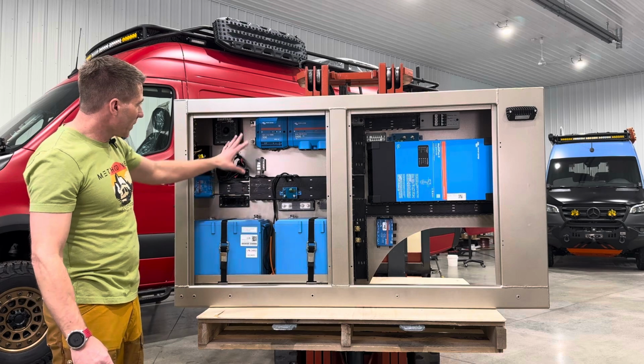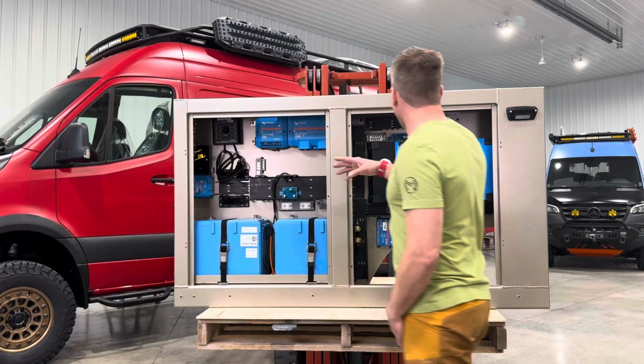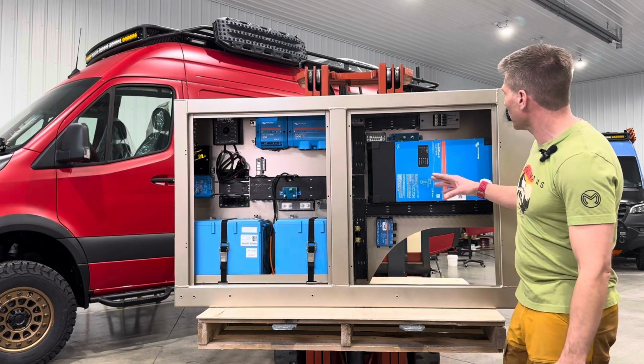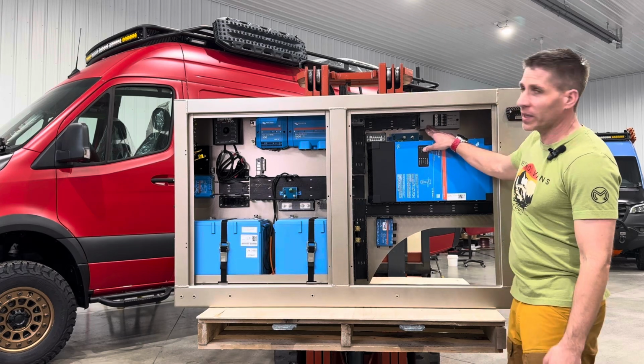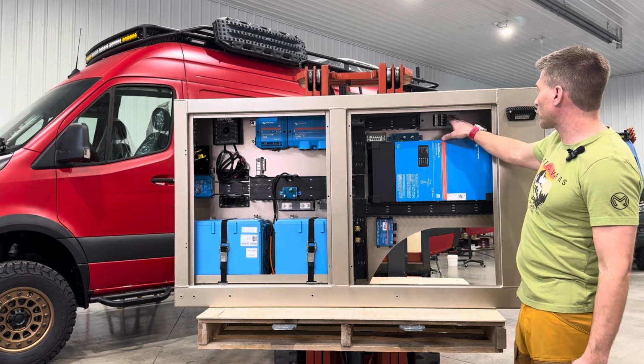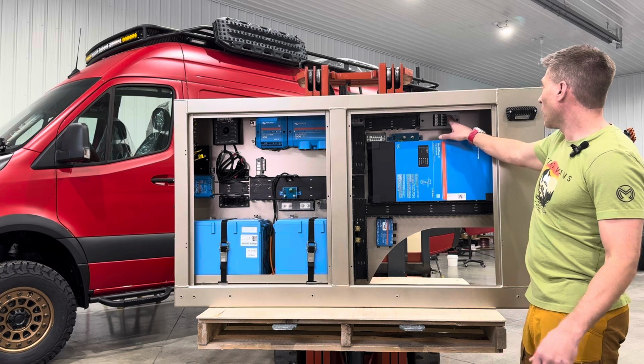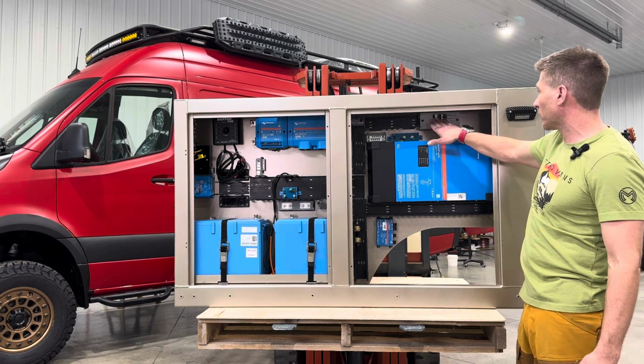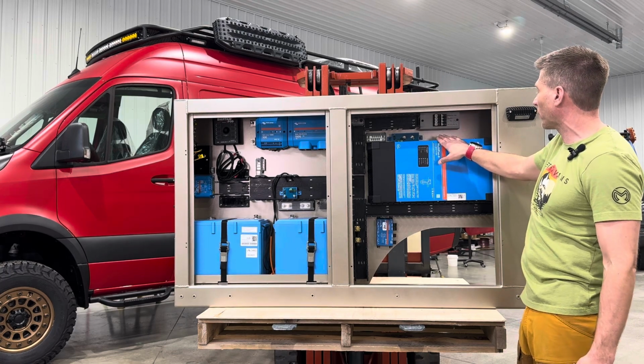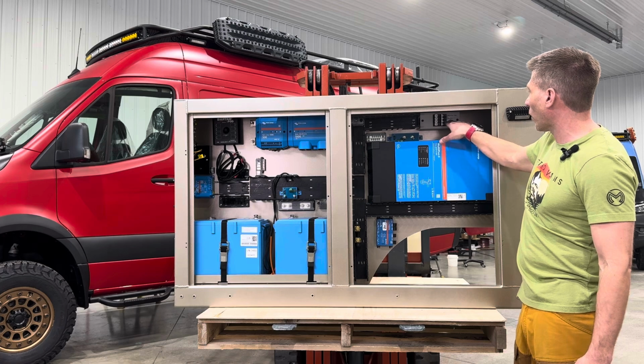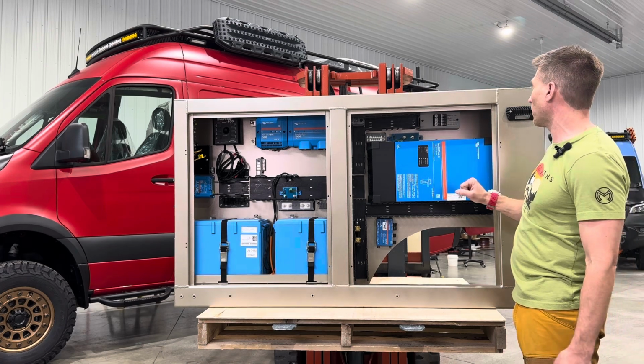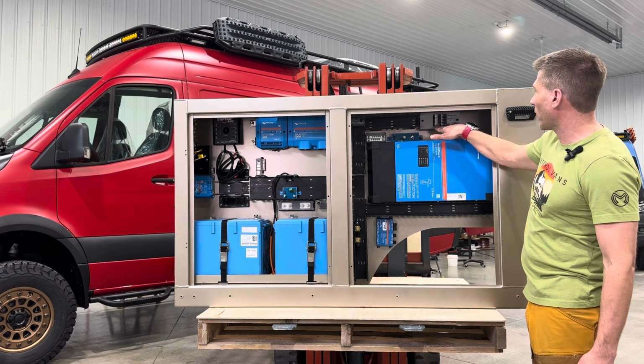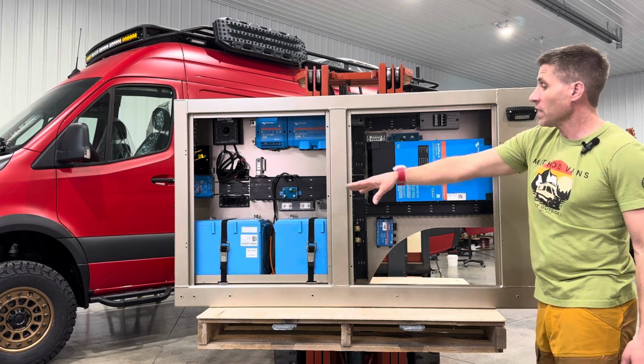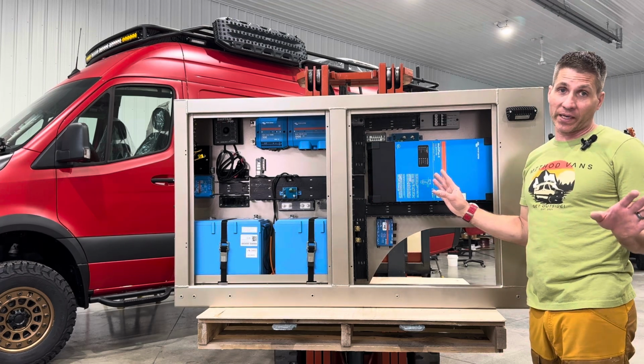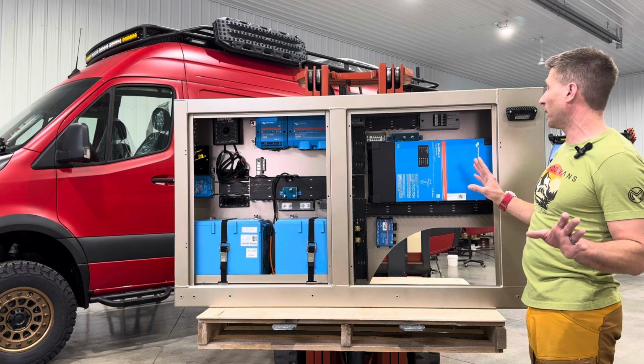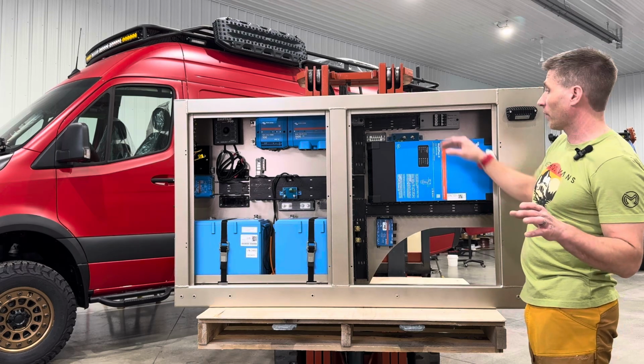From here, if we pop over, we have some other componentry. We have a breaker box with our solar disconnect - solar in and solar out - which we can turn on and off inside this breaker box. We have a breaker for our alternator regulator inside this box, and we also have a breaker for our battery heating. So if we want to, in the summer, just turn the battery heating off to have no risk of it coming on by mistake or having an issue, we can turn off the breaker.